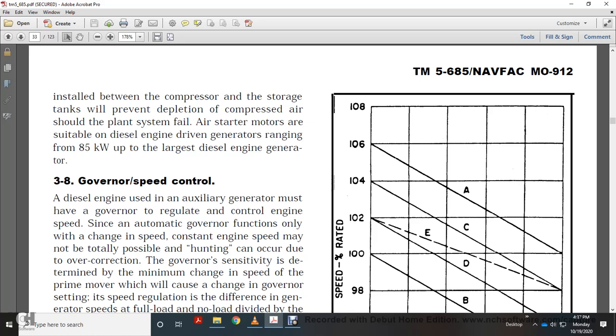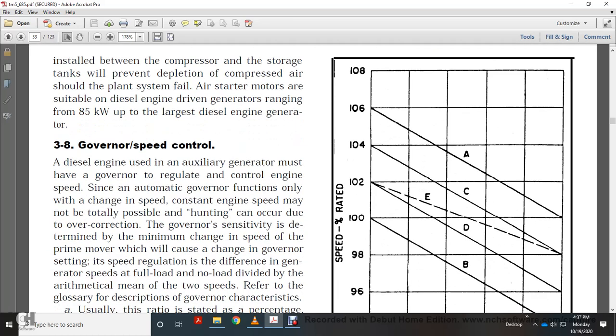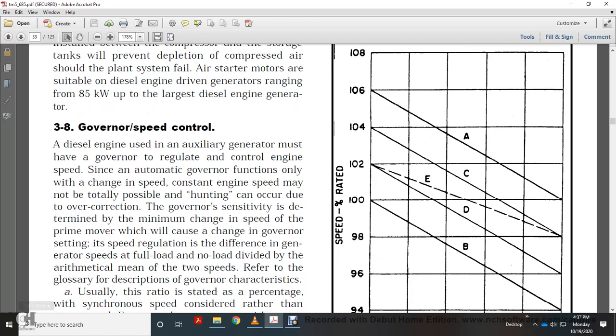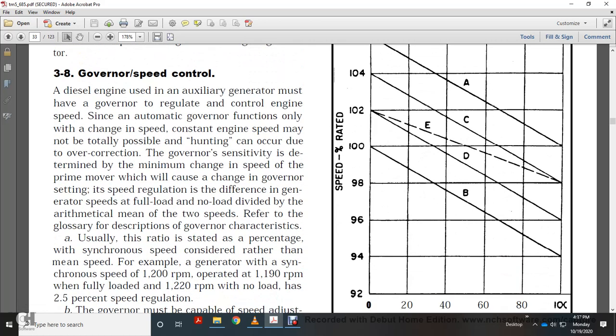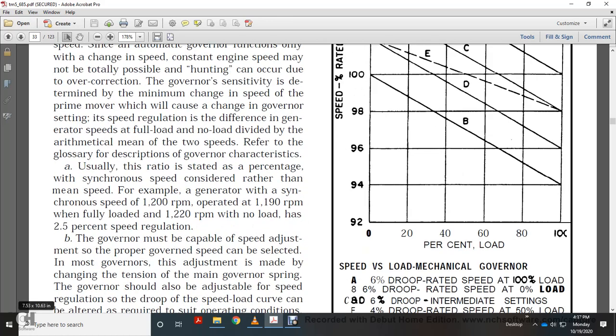Governor sensitivity determines the minimum change of speed detectable. Speed regulation is the difference in generator speed at full load versus no load, divided by the arithmetic mean of the two speeds. Usually, the ratio is stated as a percentage of synchronized speed. For example, a generator with a synchronized speed of 1,200 RPM operating at 1,190 RPM fully loaded, with 1,220 RPM at no load, has 2.5% speed regulation.